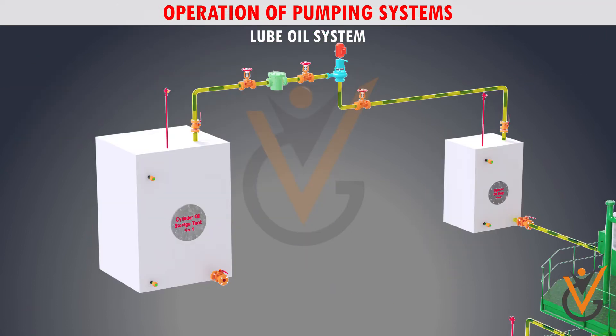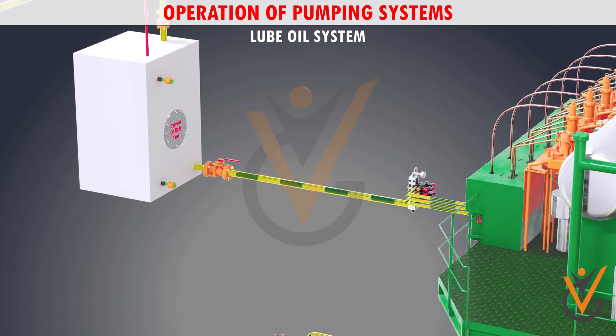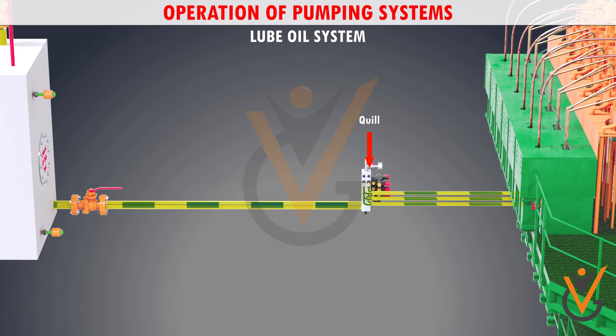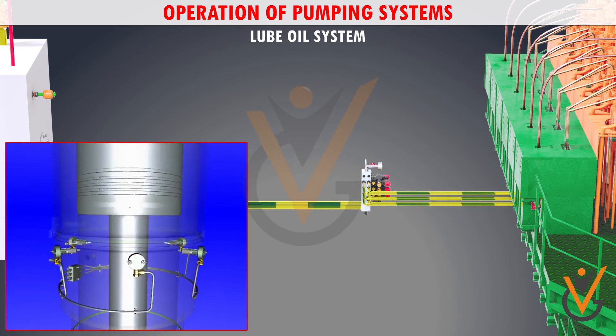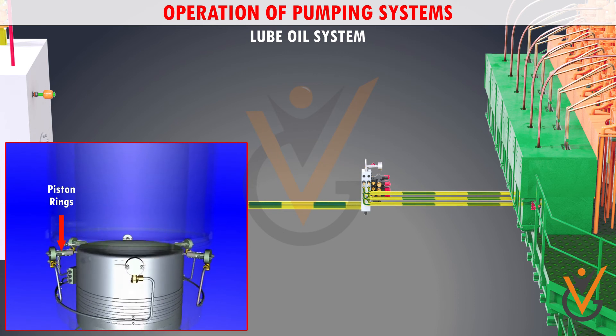The load-dependent lubrication of the cylinders is performed by a separate cylinder lubrication system. The cylinder oil is kept in a storage tank placed a minimum of 3000 millimeters above the cylinder lubricators, from where it is transferred to the cylinder daily oil tank for engine usage. It is fed to the engine cylinders by a quill fitted in the liner.